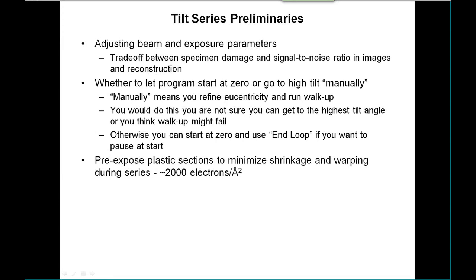One of the decisions you have to make is whether to let the program start at zero or go to high tilt manually. By manually, we mean that you would make sure the eucentricity is refined before you start, and you would either run the walk-up or tilt-up by pushing the button. You might do this if you're not sure you can get to the highest tilt angle or if you think the walk-up might fail. Otherwise, you can start at zero and use the end loop button if you want to pause after the first tilt is reached and make sure things are good.